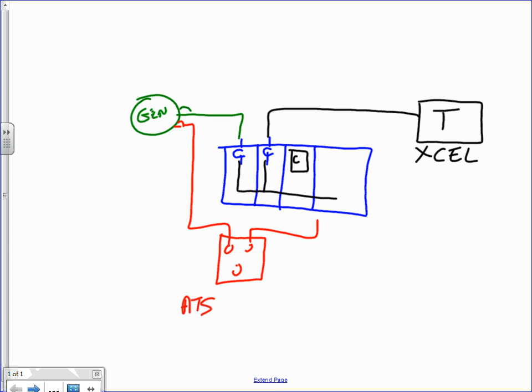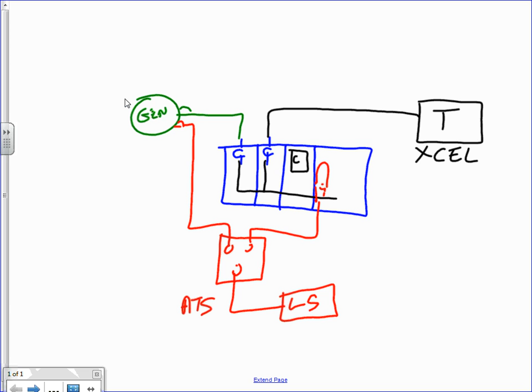So this is my code required support, and that wiring is separate from my optional building support that I've provided, more from a business perspective. This is my code required. You have to work out details and need to provide a power system and life safety backup system in that manner. I guess for clarity, normally this transfer switch should be on utility, and then my alternate source would be genset.